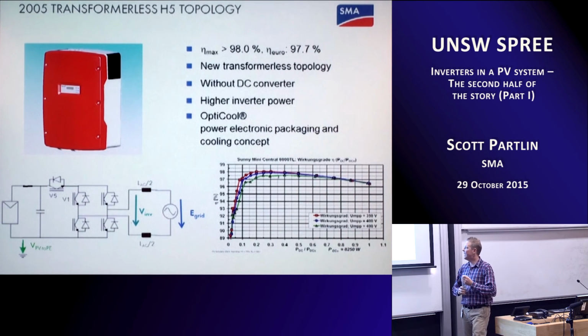The improvement to that circuit was what SMA then came up with, which is the H5 bridge, the 5 IGBTs that you can see there, and that's the illustration that I showed earlier, which saw efficiencies peaking at over 98%, weighted efficiencies almost up to 98%. But again, that progression is always seeing a reduction in components, a reduction in complexity, which is always leading to an increase in the reliability of the inverter.